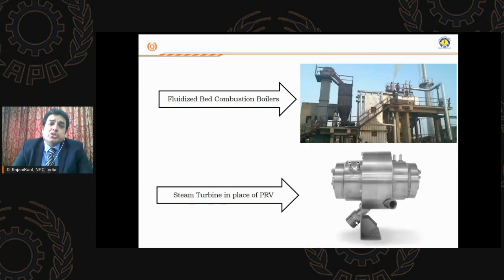The boiler is available. So these boilers will come into a medium term investment, where you get back your payback in 2 to 3 years, depending upon the loading and the kind of operation hours you are having. Normally, whenever you generate steam using these boilers, what we have observed is you generate at a high temperature and pressure from your boiler, and you keep some leverage to go to the end of the plant. Maybe you require 6 kg, you generate 8 kg. But when it reaches your equipment, you don't require that much pressure.